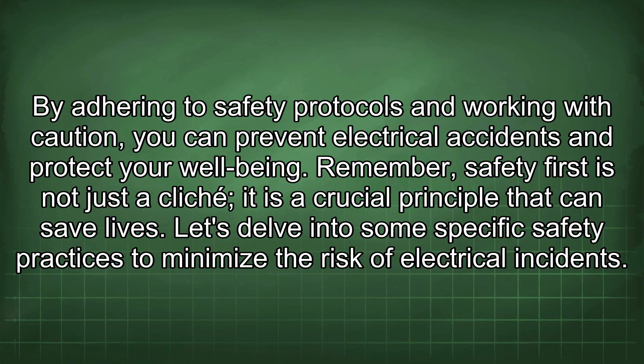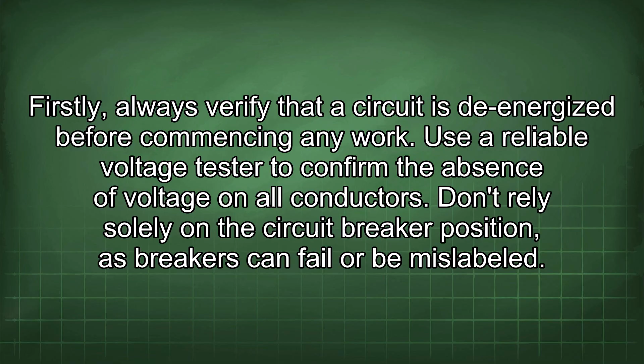Firstly, always verify that the circuit is de-energized before commencing any work. Use a reliable voltage tester to confirm the absence of voltage on all conductors. Don't rely solely on the circuit breaker position, as breakers can fail or be mislabeled.